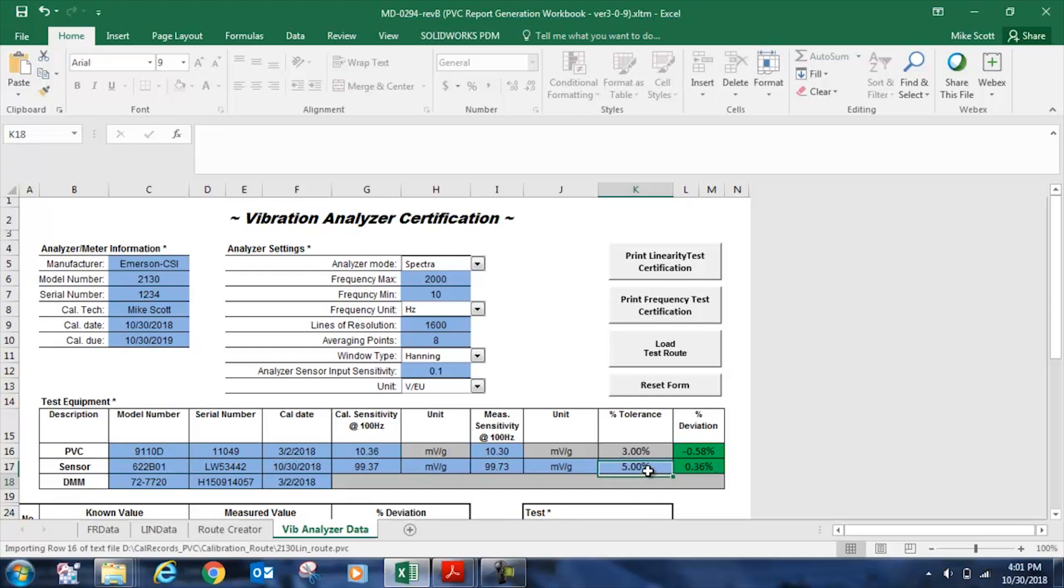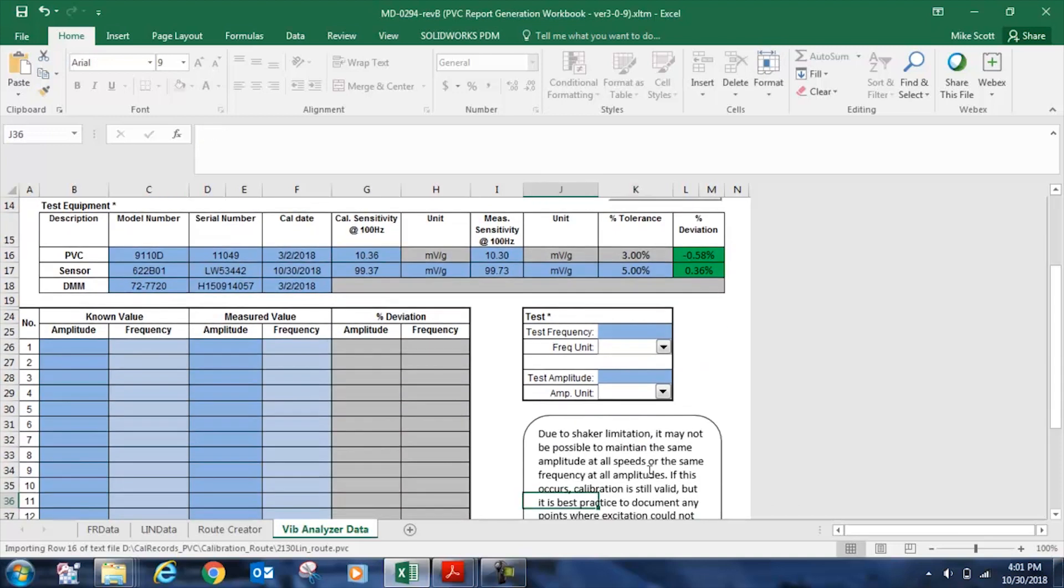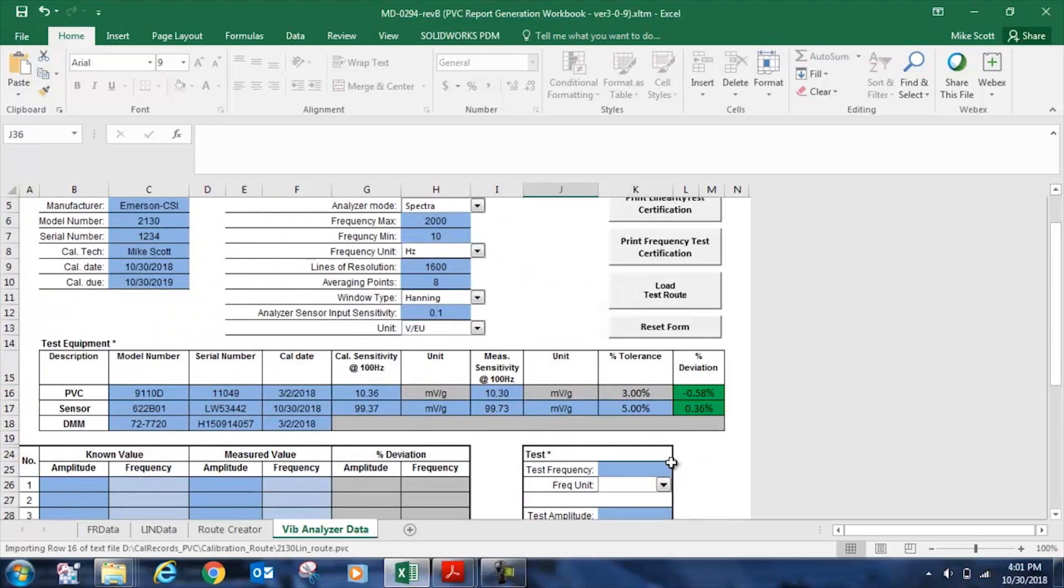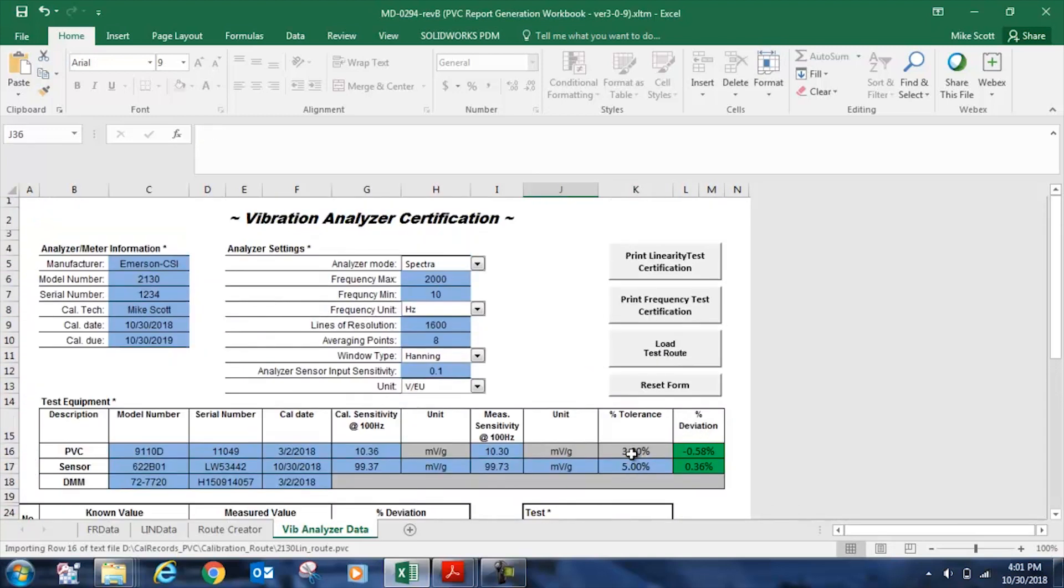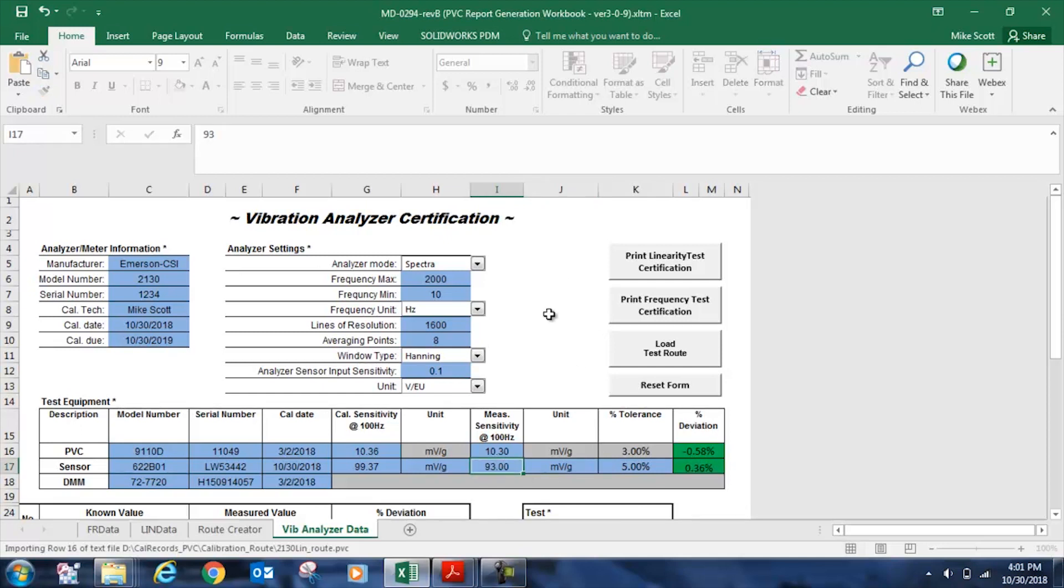The deviation tolerance for the portable calibrator can't be changed. This 3% value is locked in, and that's our accuracy specification for the 9110D.